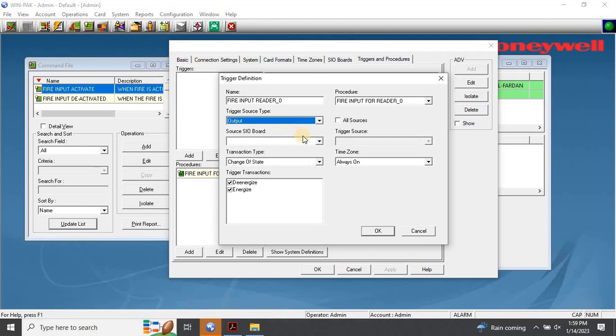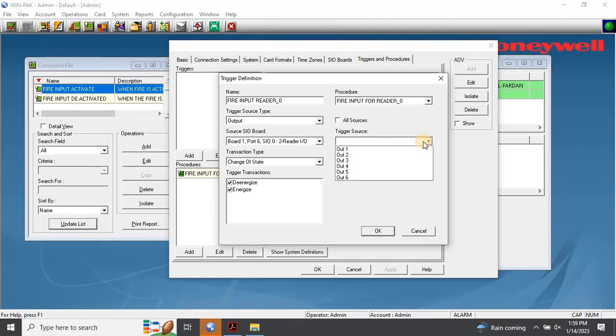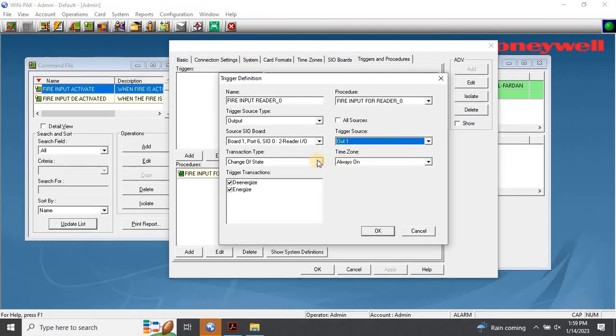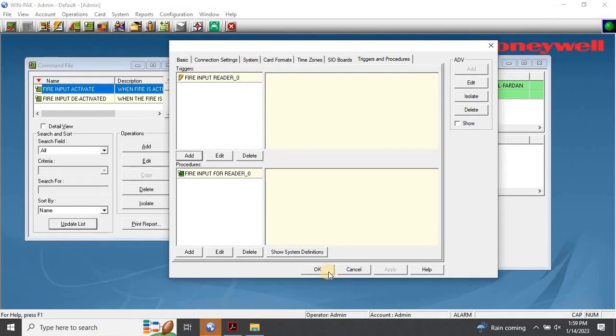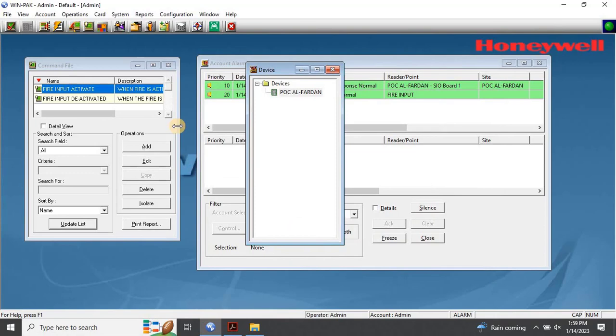Select a source SIO board — only the boards configured for this panel are displayed in the list. Select the SIO board in which you want to select a trigger point. In the Trigger Source list, select the exact point on the SIO board that you want to use as the trigger point. In the Transaction Type list, keep the default. In the Trigger Transactions, keep it as default. Click OK to save the definition and return to the Triggers and Procedures dialog box. You can view the list of triggers and procedures, and select a trigger to see its definition on the right side of the window. Click the plus sign to expand the events view. Once you have completed adding triggers and procedures, click OK to complete the configuration.